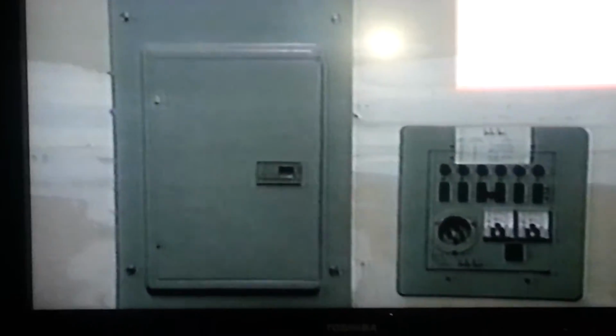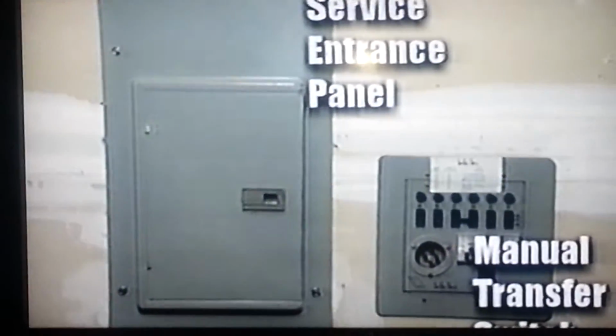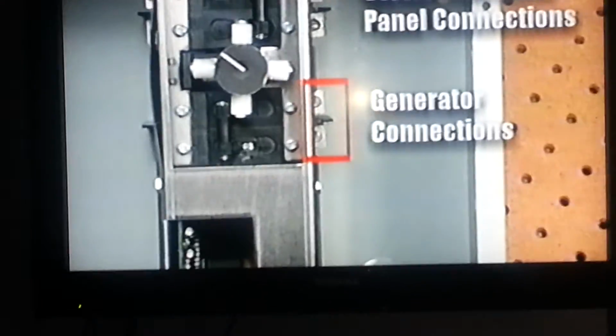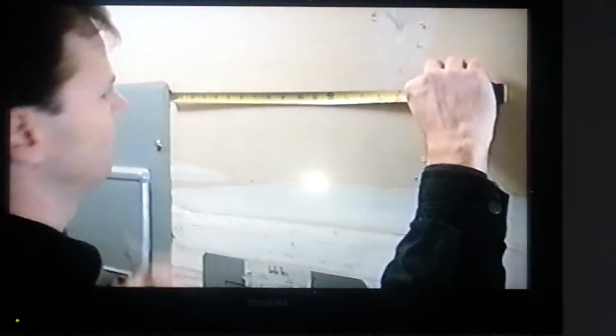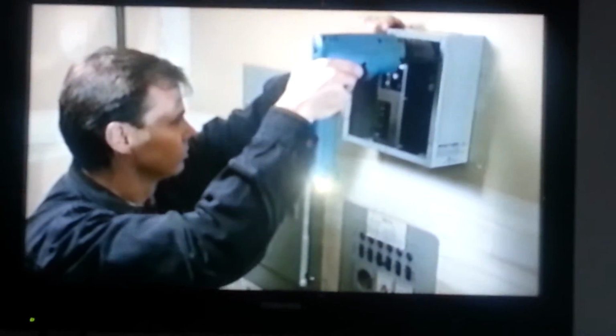To prepare for installation of the ATS transfer switch, select a location that will allow easy access for wiring to both the service entrance panel and the manual transfer switch. Keep in mind that the connections for the service entrance panel and the generator are on the right side of the ATS transfer switch, and the connections for the manual transfer switch are on the left side. When you've selected the best location, find the studs and measure and mark accordingly. Then, mount the transfer switch unit to the wall securely with appropriate screws and wall anchors.